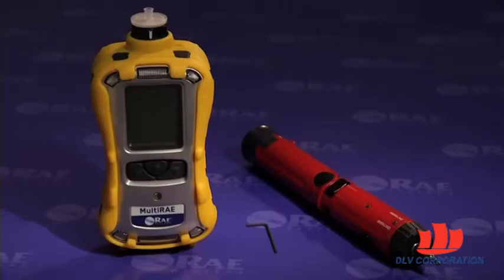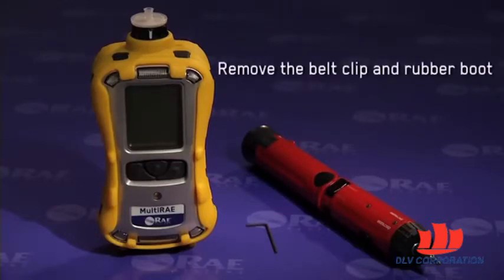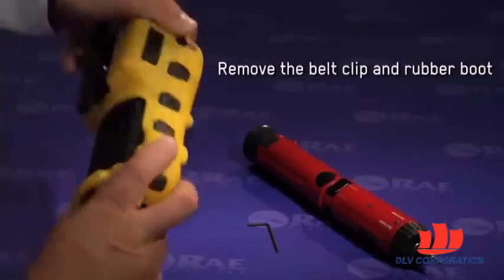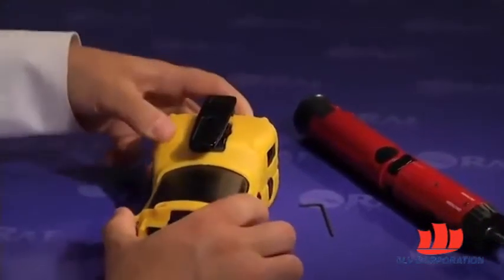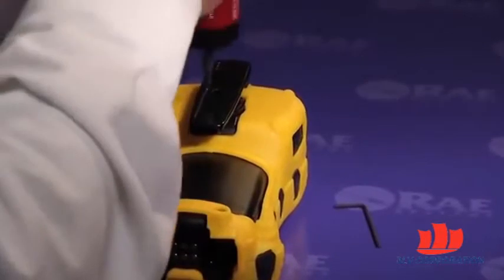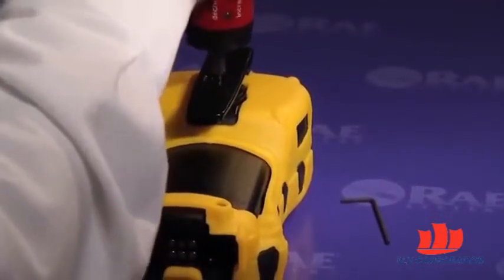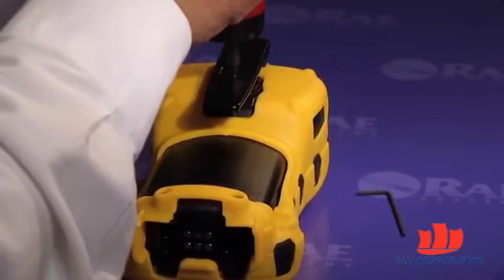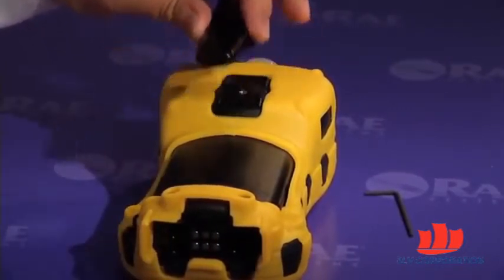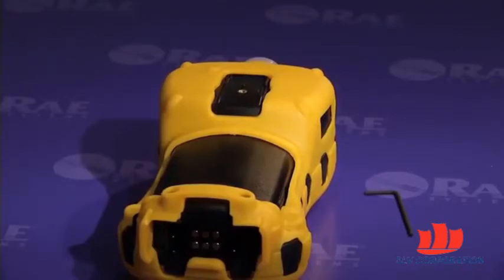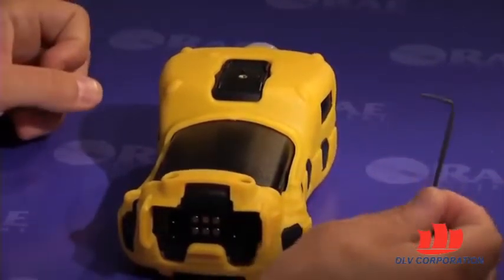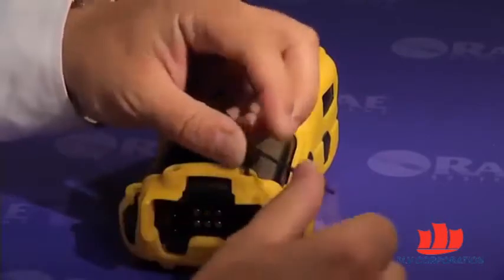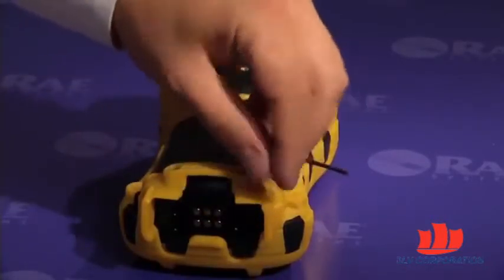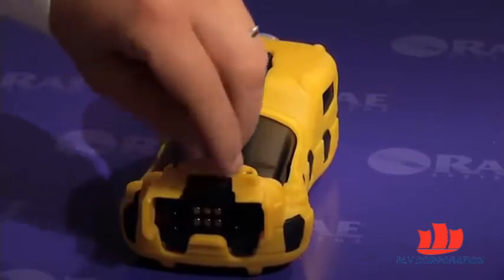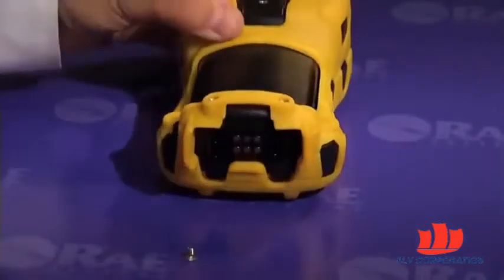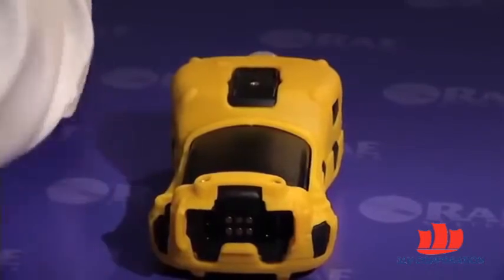The sensor replacement process on the MultiRAE starts with the removal of the belt clip and the rubber boot. Turn the MultiRAE face down and unscrew the Phillips screw that holds the belt clip in place. Set the belt clip aside. Now use the included hex tool to remove the two hex screws holding the rubber boot attached to the instrument. Set the screws aside.